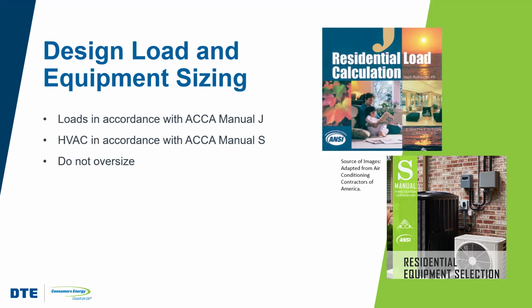Now, if we were talking about grandma's apple pie, bigger might be better. But when it comes to HVAC equipment, bigger is not necessarily better. A good design does not use HVAC equipment that is oversized, because oversized equipment often cannot modulate low enough to match the actual load. So that means that it's going to use more energy than necessary to meet the demand. And since it can't modulate down too well, larger equipment or oversized equipment often cycles on and off more frequently. This reduces its life expectancy.